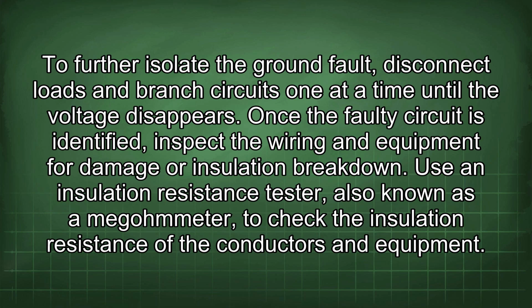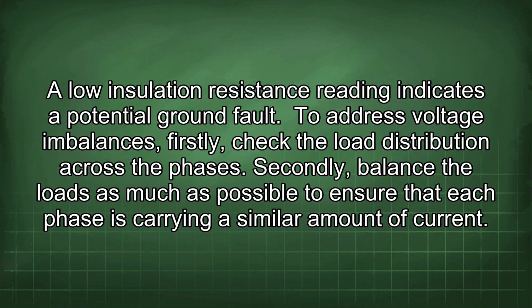To further isolate the ground fault, disconnect loads and branch circuits one at a time until the voltage disappears. Once the faulty circuit is identified, inspect the wiring and equipment for damage or insulation breakdown. Use an insulation resistance tester, also known as a megger, to check the insulation resistance of the conductors and equipment. A low insulation resistance reading indicates a potential ground fault.